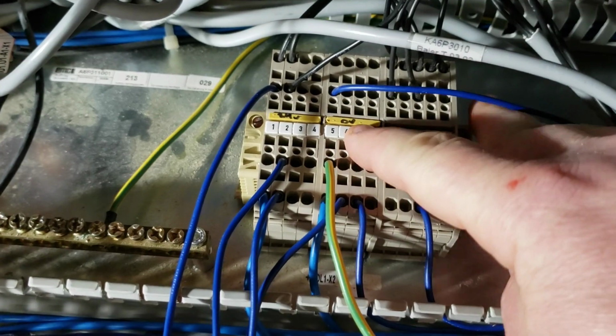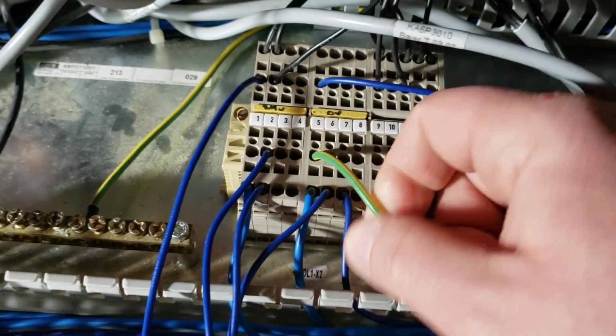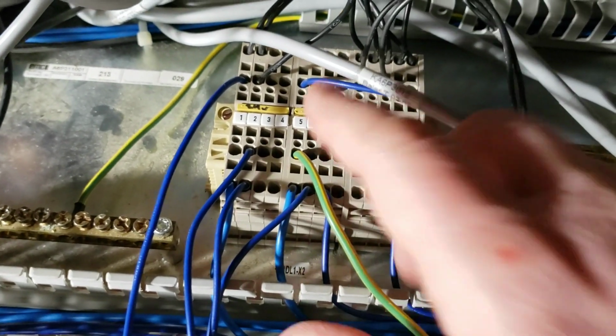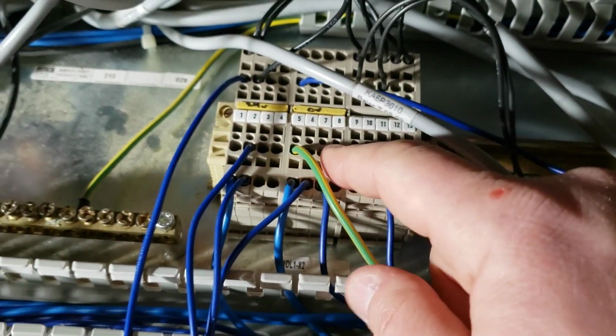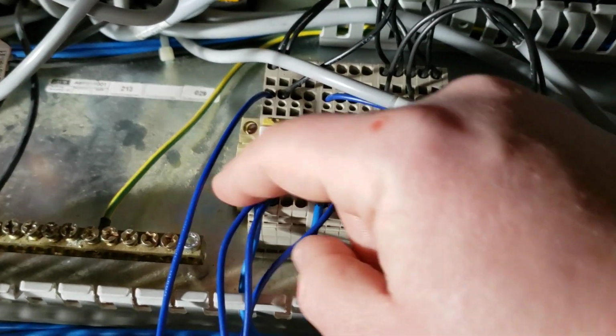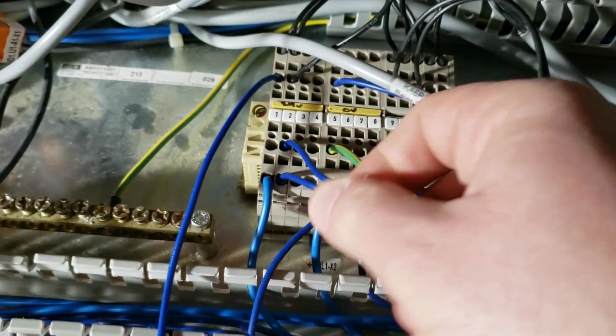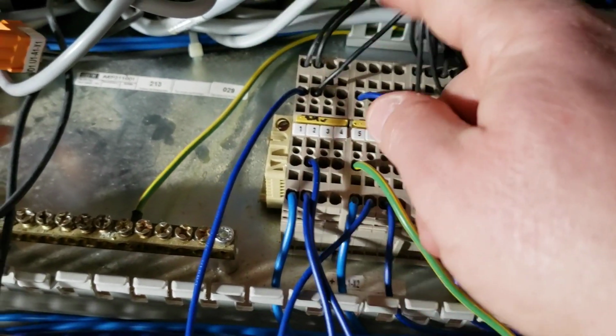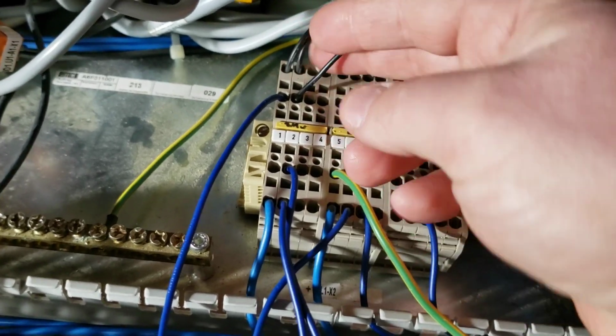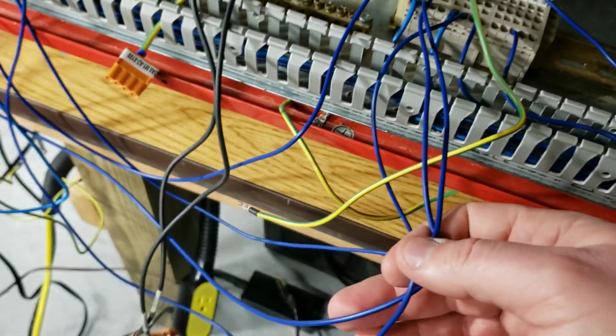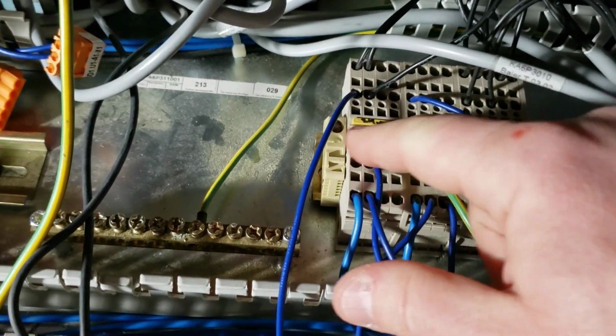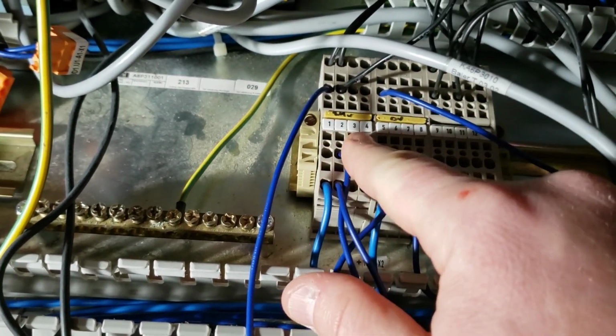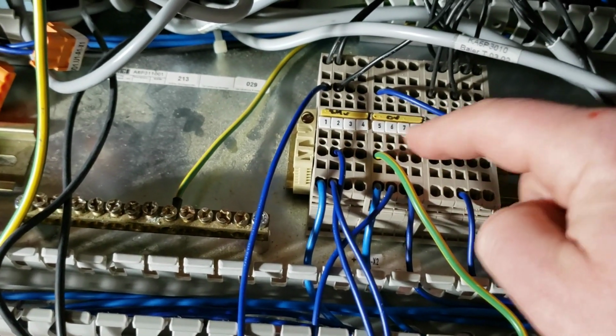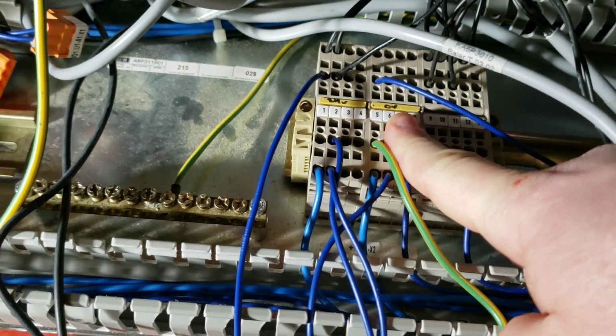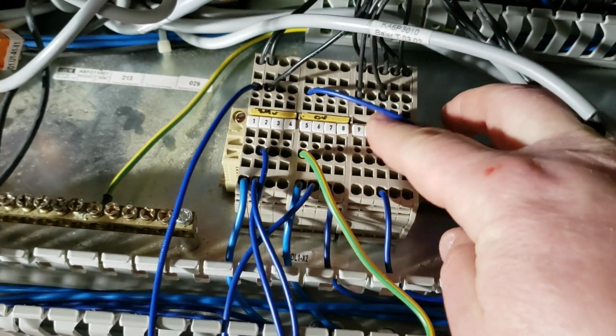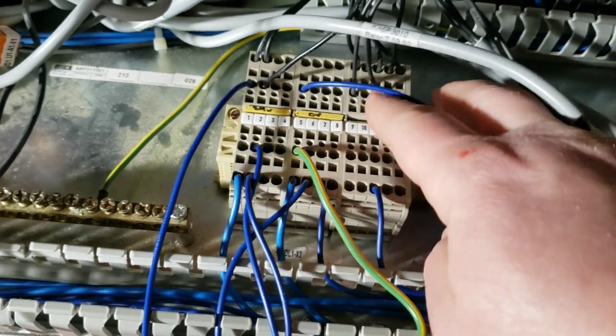I got marked 24 volt and 0 volt common. 0 volt common on this machine actually ties not only to common on the transformer, but also common as an earth ground. But I've got them tied into position number 2 here, which is also shared between these, but they don't interfere with one another. This is just providing 24 volt out to all of the devices attached to this section of terminal block, and then this terminal block here is just providing the common return for those. And then these are the individual switches that go out from one to the next, to the next, to the next.